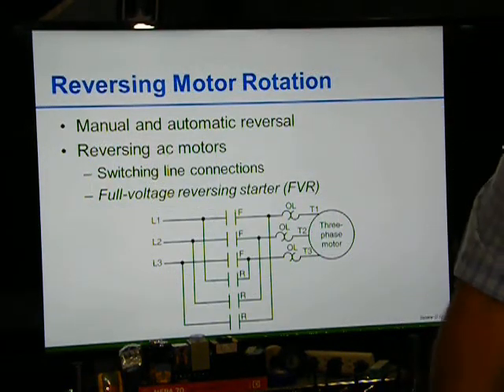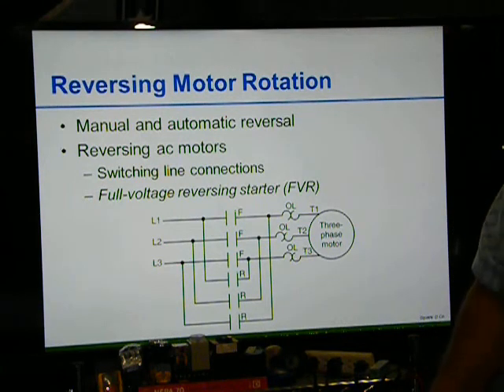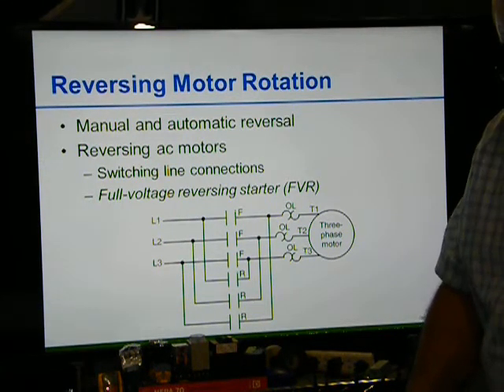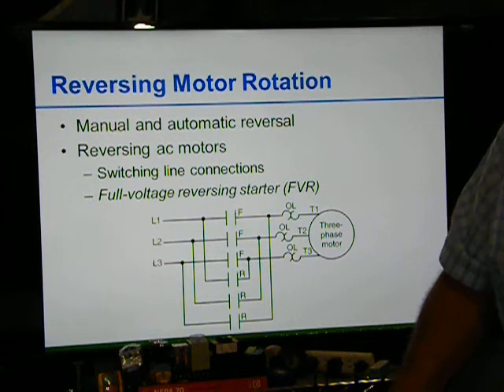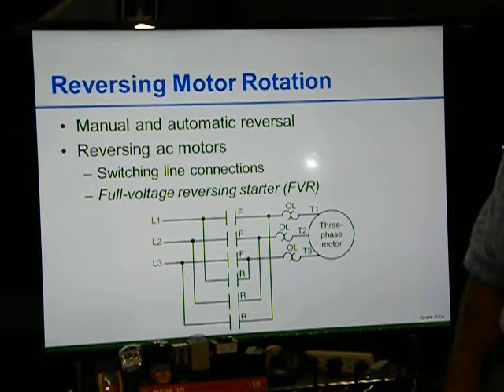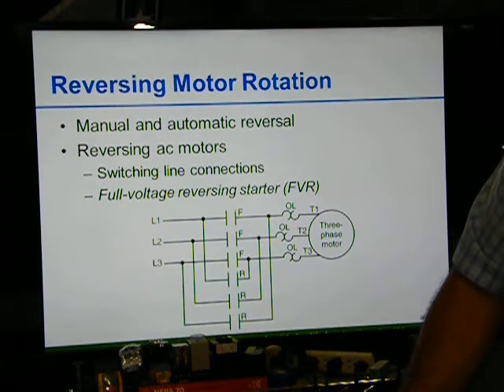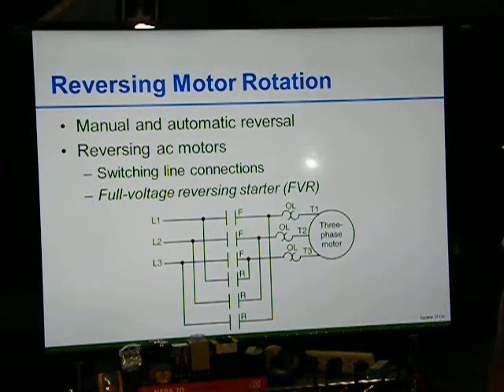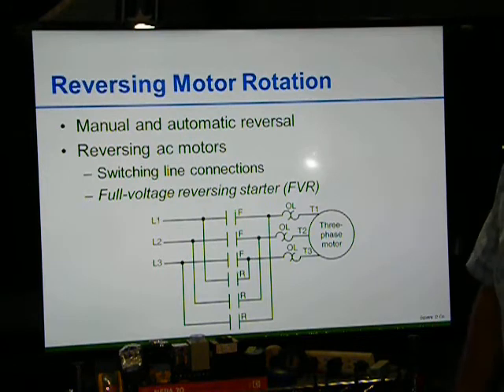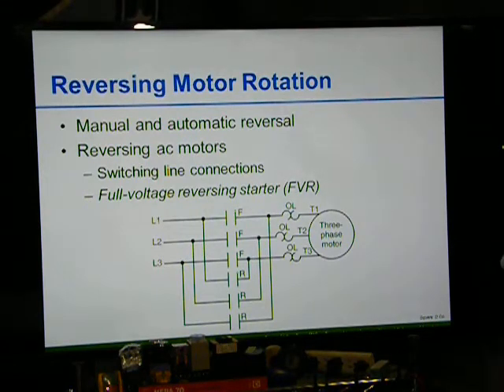Reversing motors. Okay, reversing motors. This says it is often necessary to be able to run a motor in forward and reverse. Motor direction can be manually reversed by switching connections. Some motor controls can reverse direction automatically. So you can use a switch. All the switch does is, you hit the stop button, hit a switch, and it just reverses two hots.